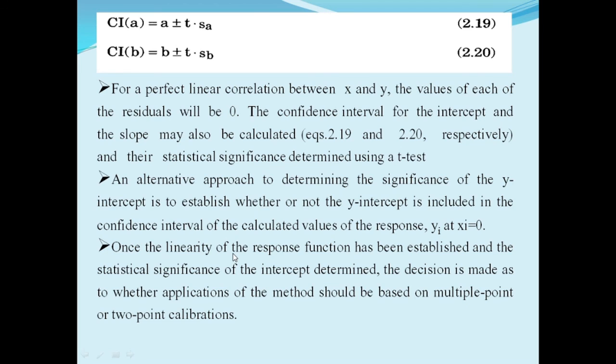Once the linearity of the response function has been established and the statistical significance of the intercept determined, the decision is made as to whether application of the method should be based on multiple point or 2-point calibration. Alternatively, the initial analysis of the response function by least square unweighted linear regression may indicate that a nonlinear response function is more appropriate.